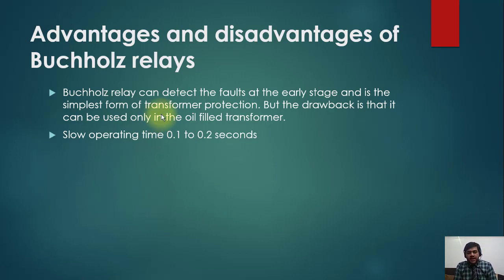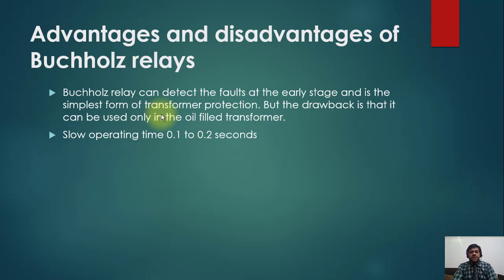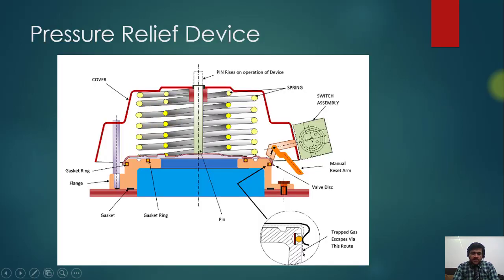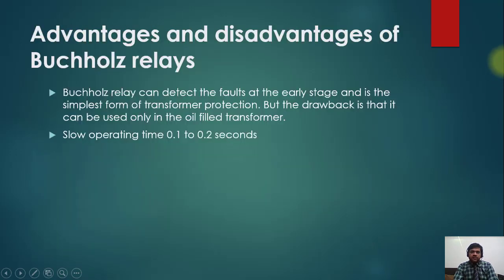Regarding the advantages and disadvantages of the Buchholz relay: the Buchholz relay can detect faults at an early stage and is the simplest form of transformer protection. However, the drawback is that it can only be used on oil-filled transformers. Another drawback is the slow operating time of 0.1 to 0.2 seconds. Thank you very much.